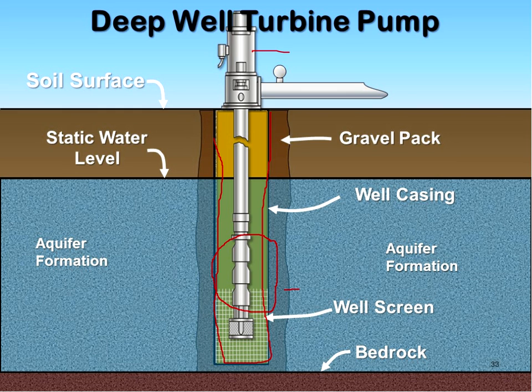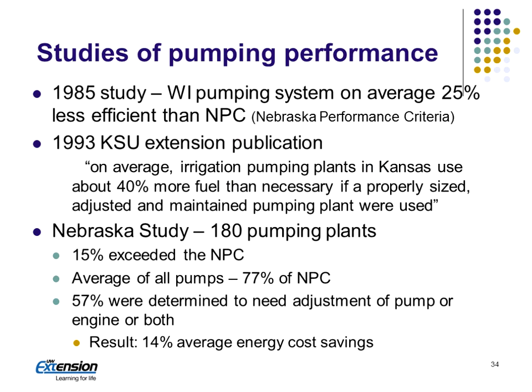So when we have to modify a pump, we have to pull this whole thing out of the well, and we typically are either changing the size of the impeller, or maybe we reduce the number of stages on the pump, depending on what the requirements are.